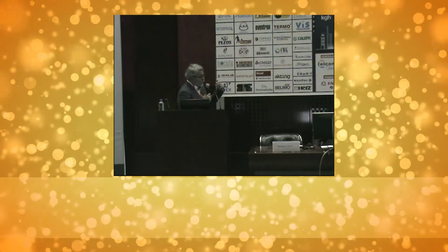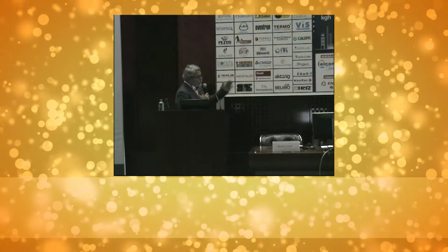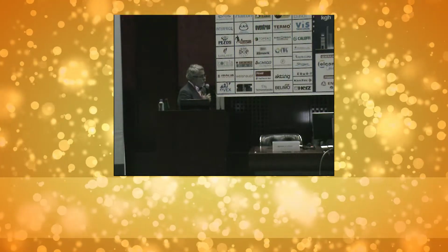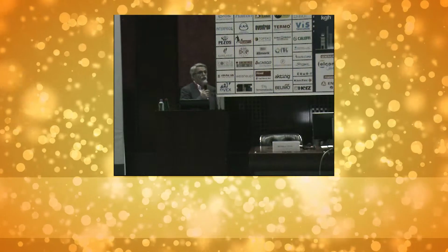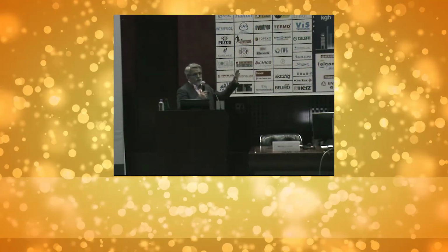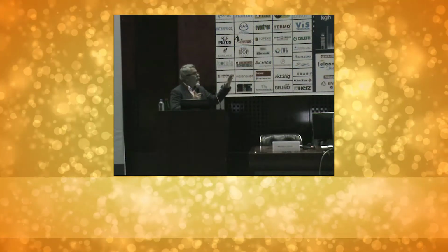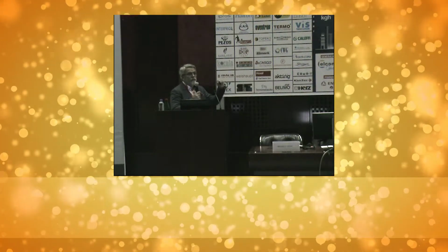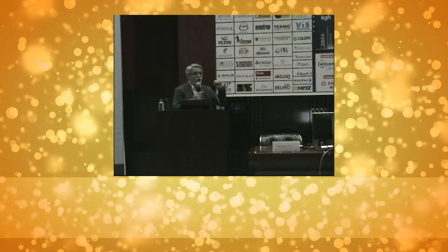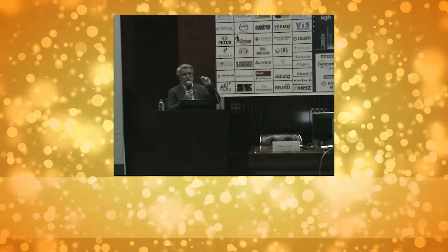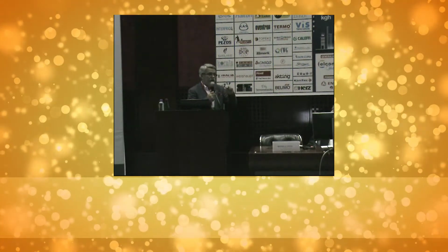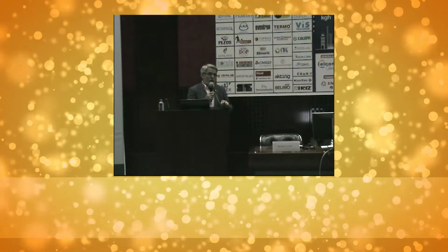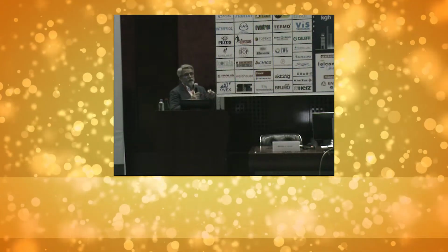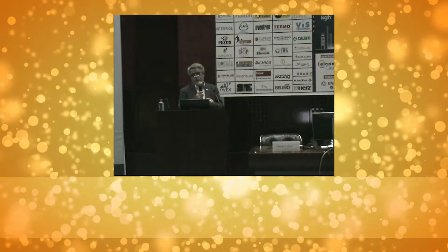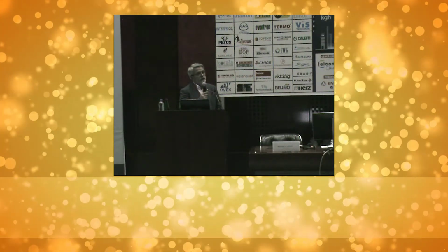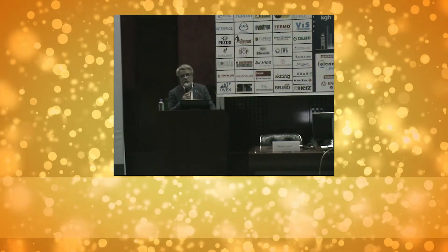Also, I want to say something more, because I want to improve this plant, and now I'm making a new study for changing the brine. In this case, as I told you, it's a mixture of water and glycol. For the future, I want to use a mixture of water and ammonia. Ammonia is not only a good refrigerant, but could become a very good secondary fluid. Because using water and ammonia, after the calculation that I have made on paper only, there is a decrease of the energy for pumping.